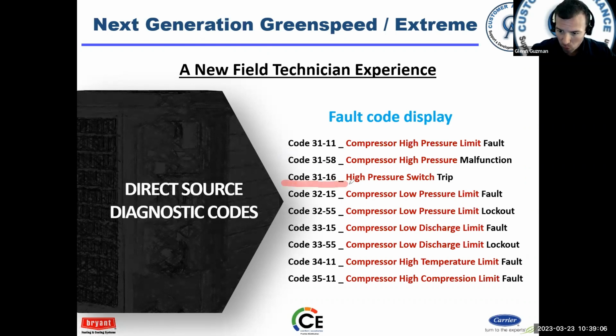For example, if we look at the 31s here, all of these are 31s. They all have to do with high pressure. Some is a high pressure trip, high pressure malfunction, or a limit fault. So the child code will give you a little more clarity on the high pressure issue. The 16 is high pressure switch trip, the 58 is a malfunction. It's shutting the unit down. The fault is just a fault. It's going to try and ride through the fault, but if it happens again, eventually it'll malfunction. That's kind of how you read those codes.